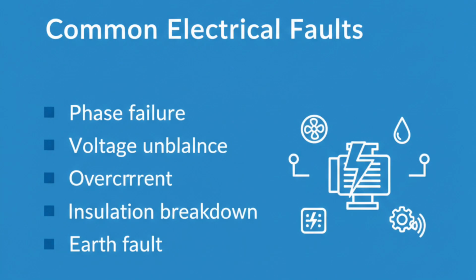Now let us consider electrical faults. Phase failure or single phasing is extremely dangerous because it causes high current in the remaining phases and rapid overheating. Unbalanced voltage supply also results in unequal stator currents and torque pulsations. Overcurrent may occur due to overload or jammed mechanical load. Insulation breakdown happens when insulation ages, absorbs moisture, or is damaged by overheating, leading to short circuits or earth faults.